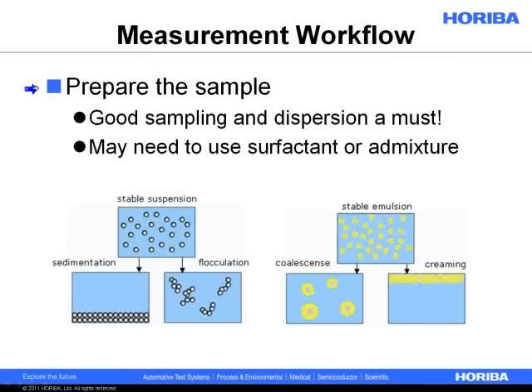The next few slides cover the measurement workflow. Many of you already use laser diffraction instruments, so this will be a bit like review. The basic measurement workflow is: you need to do something to prepare the sample many times. Whether it's arriving as a powder or paste, a lot of times samples aren't ready for direct addition to the analyzer. If you can't be absolutely confident that what you're putting into the analyzer is representative of the sample you have in your lab, it's going to be more difficult to trust the data that comes out. Sort of garbage in, garbage out — though that's a bit harsh.